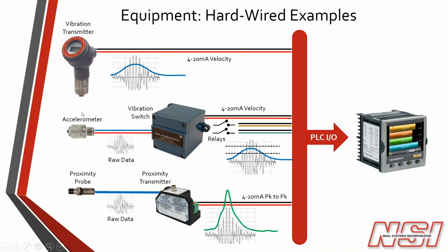The next one down here is an accelerometer going into a switch. The switch is interpreting that acceleration signal for that 4 to 20, just like the transmitter did, but it's also looking at some thresholds to trigger relays. If that RMS signal goes above the first threshold, the alarm threshold, you're going to get one relay that says, hey, look, something's happening to this asset, needs attention. Then typically you set up the other relay to do shutdown functionality, and if you exceed that second relay, the machine's going to be turned off automatically.